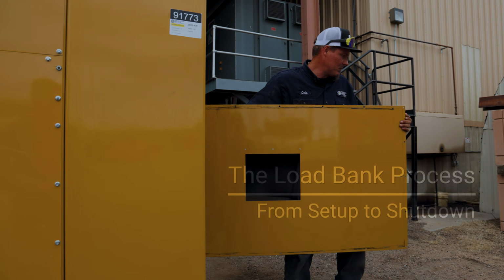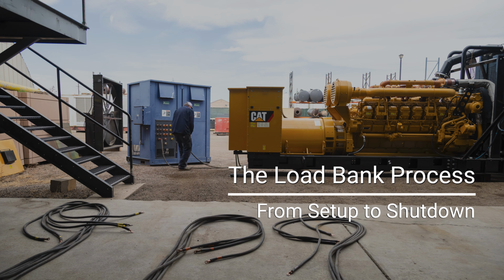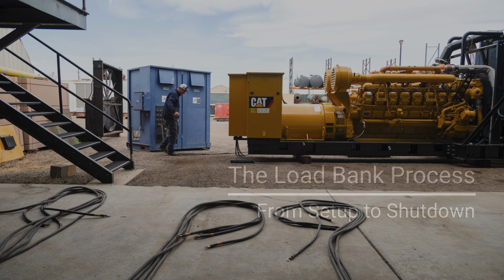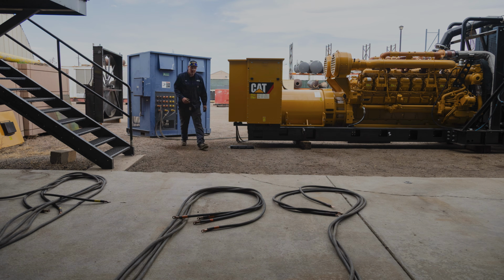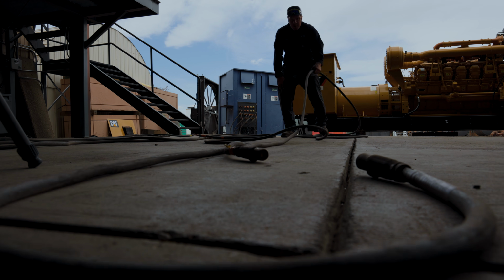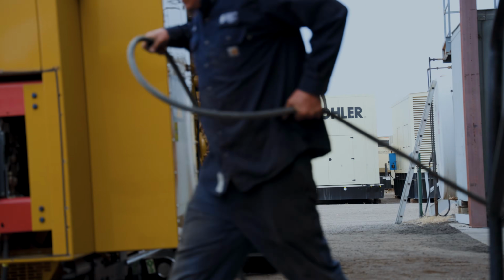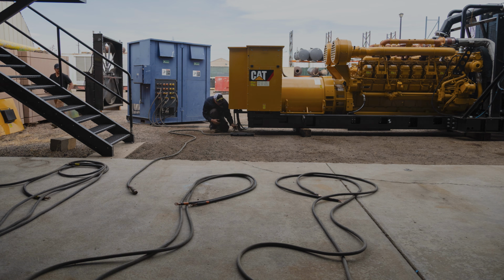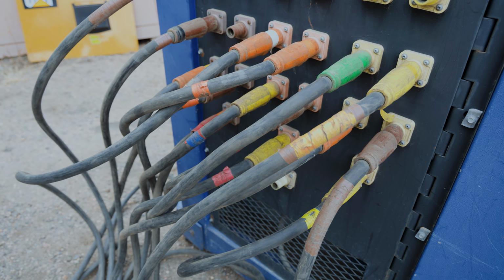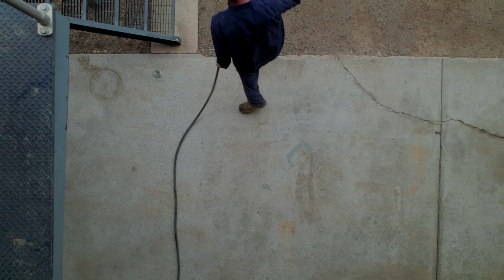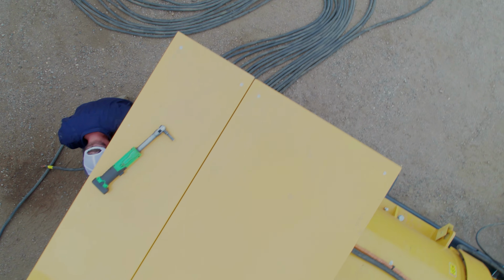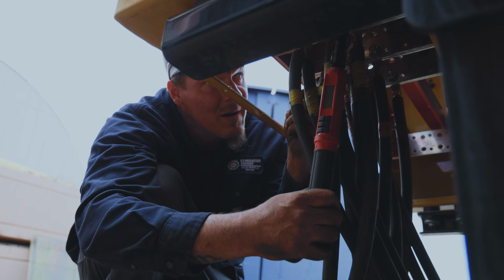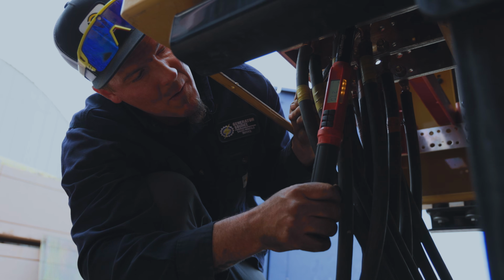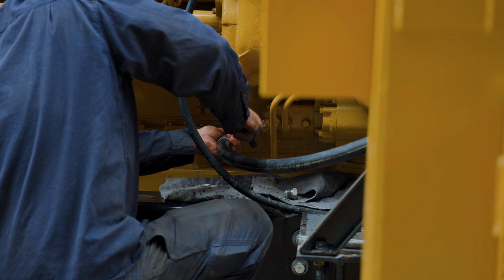So let's walk through how a load test is actually performed. After we verify that the unit is good during our 31-point inspection, we then connect the cables to the unit. 2000 kW Caterpillar. It's rated for 3007 amp. Due to the altitude where we're at, we load bank the units up to 80%, and each piece of cable is rated for 400 amps. So what we do is calculate the percentage to what kW that's going to be at 80%. That will tell us how many cables we're going to need to perform the test.